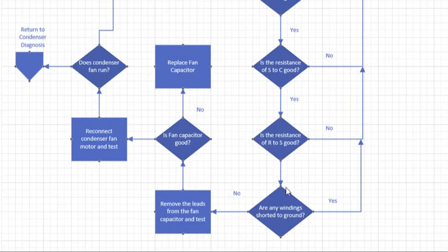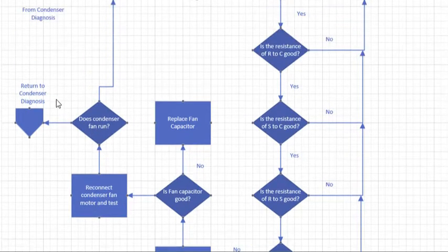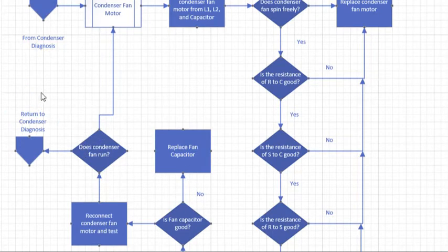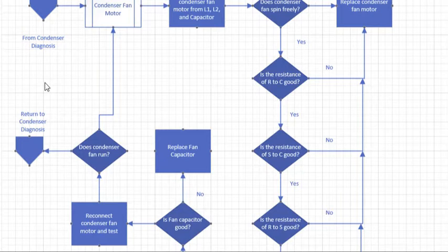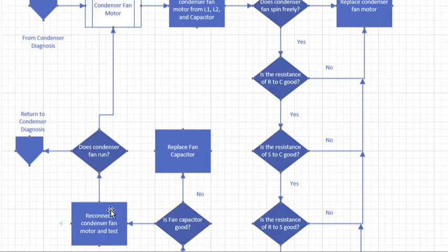If everything tests out on the fan, you're going to reconnect the condenser fan motor and test it. Does it run? If it doesn't run, you have to go back and test it again. If you have power to this motor, which we've already established in the condenser tests, if you have power to that contactor and that condenser fan does not run, you've missed a step in here. Because if you've done all of this and you have power to the motor, which we've tested with the condenser diagnostics, that fan should run.